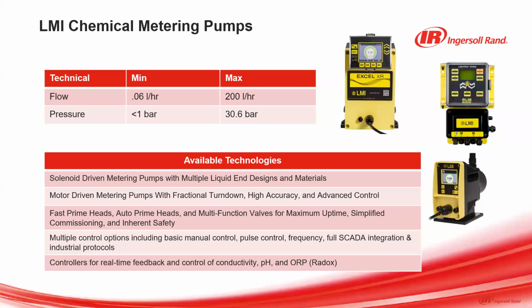On the low pressure side, the solenoid pumps and the motor driven diaphragm pumps, as well as controllers, work seamlessly together in order to balance chemistry and water, especially on the early stages of the process during the anaerobic biodigester side. Flow ranges of these pumps in a wide number of pump varieties range from 0.06 liters per hour as high as 200 liters per hour as optional flows, with significant turn down in each range. Pressures for the solenoid pumps include as low as just under 1 bar all the way up to 30.6 bars. This is really covering the full range of requirement for water treatment, as water is required for and then produced out of the process for RNG, and then must be treated in that process.